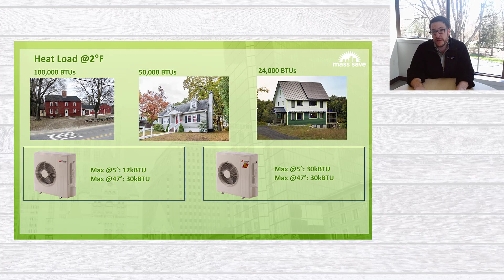If I'm looking at the heat pump on the right, which is the cold climate heat pump without a capacity drop, I would see that I would only need 2 of those heat pumps to be able to meet 100% of the building's heat load. So it's not so much that the heat pump isn't right for our homes or isn't right for our climate, or that homes can't get heat pumps, or that only energy efficient homes make sense for heat pumps. You just need to select the right equipment for the building.